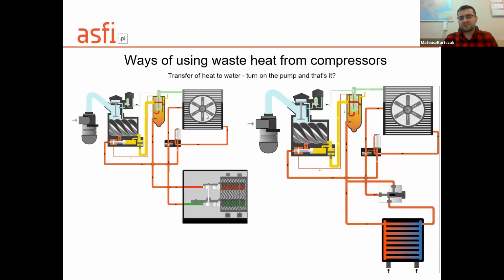On the left, you have some kind of external heat recovery unit. On this picture is a power pack. It's not necessary in this place for us. On the right, you have a typical compressor with a built-in heat exchanger. Built-in heat exchanger, please don't confuse it with heat recovery. According to the compressor manufacturer's instructions, the only thing you need to do is turn on a pump on the water side, and this is all.